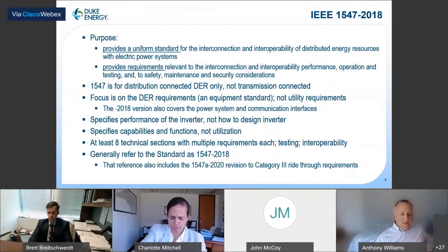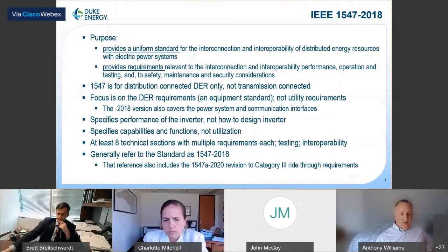1547 is for distribution connected DER only. It's not transmission connected. Those have their own standards and requirements. The focus is on DER requirements in terms of more of an equipment standard, not so much on utility requirements, still focused mainly at the DER. And then it also expands on the interface between the power system and the DER itself in terms of the power system connections, and the communication connections at the interface.